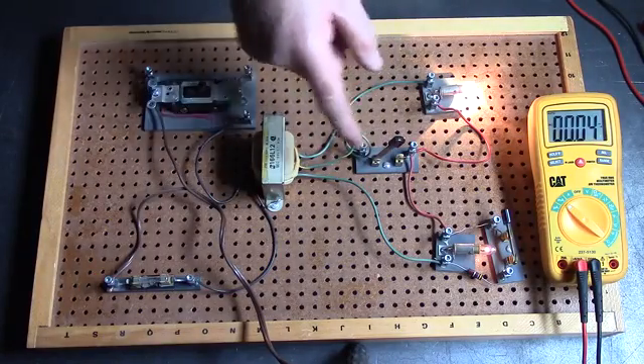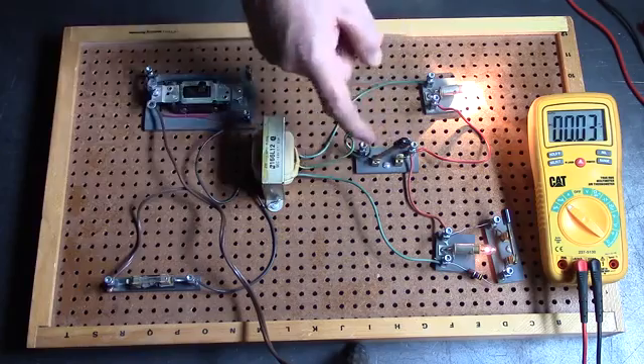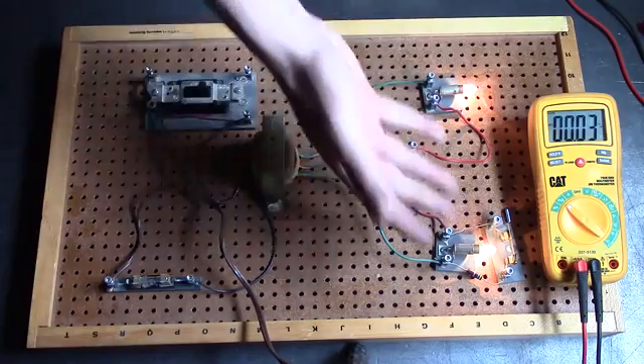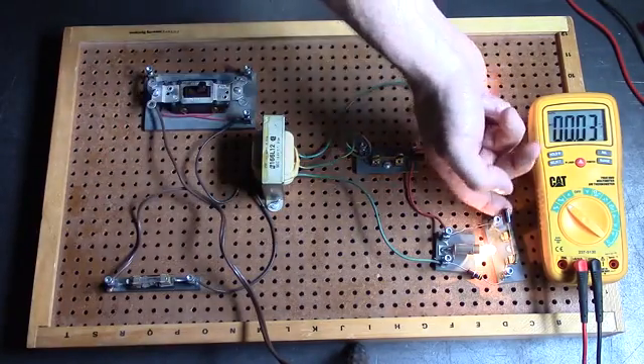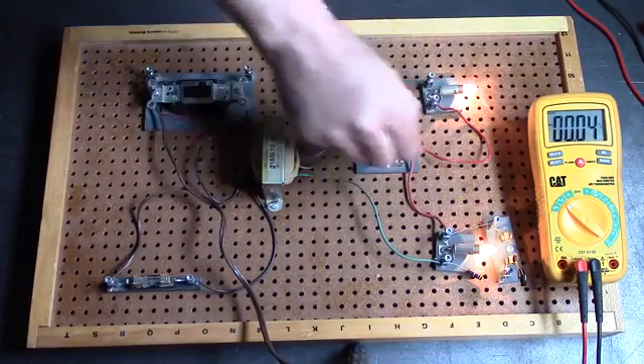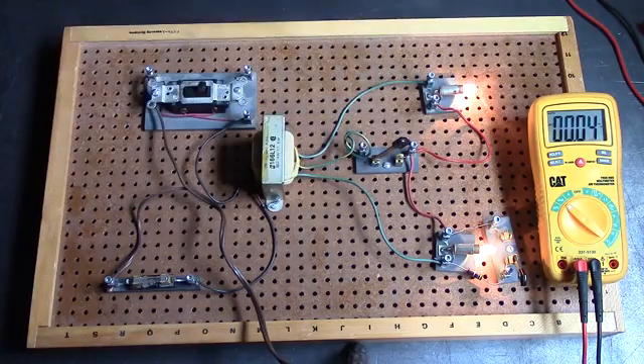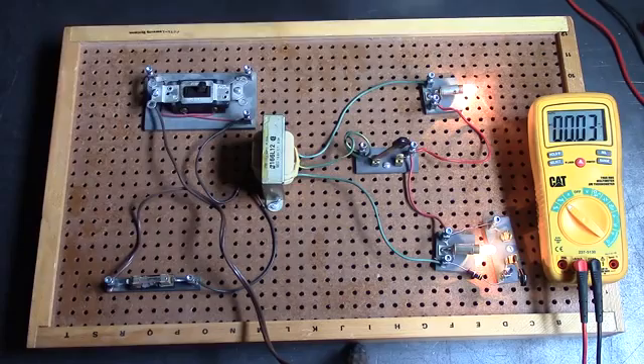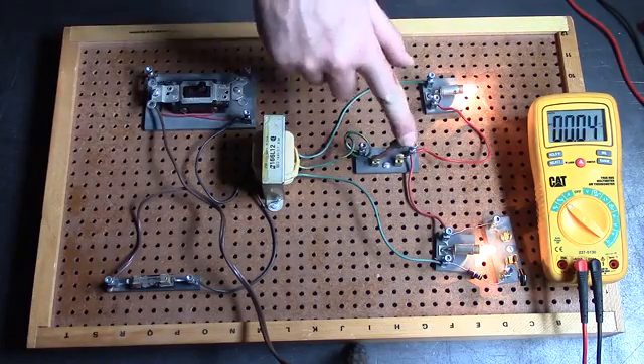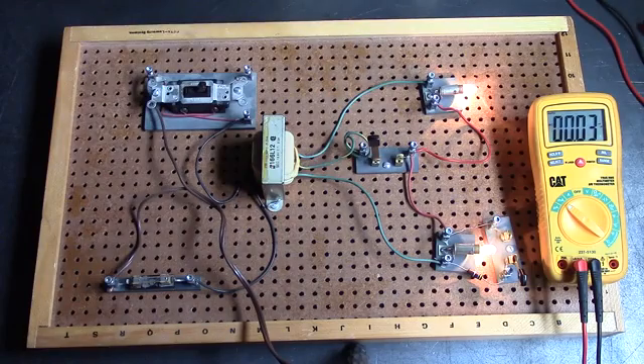And this is what's meant by balance in a three wire secondary type system. So the neutral carries unbalanced current, it only carries the difference between the two loads. If the two loads are balanced well then we don't really need the neutral at all. There's no imbalance, there's no need for current to flow in one side of the transformer secondary at any higher rate than it's flowing on the other side. So again that's what's meant by a neutral carrying unbalanced current.